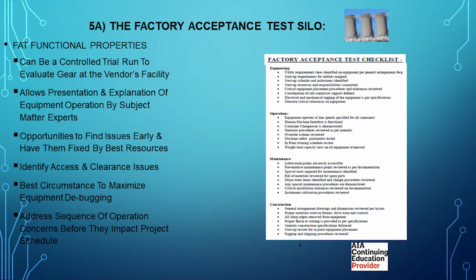So let's talk about what the individual items are now that we've provided a bit of an overview. With the factory acceptance test, the best part, if you can get one, if it's allowed and budgeted, is that you're doing a dry run with the people most knowledgeable to tell you whether or not the design engineer really knew what he was talking about.